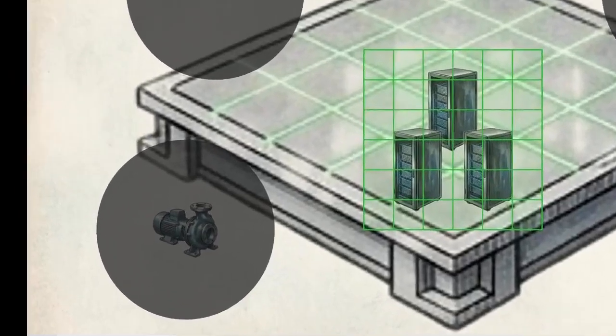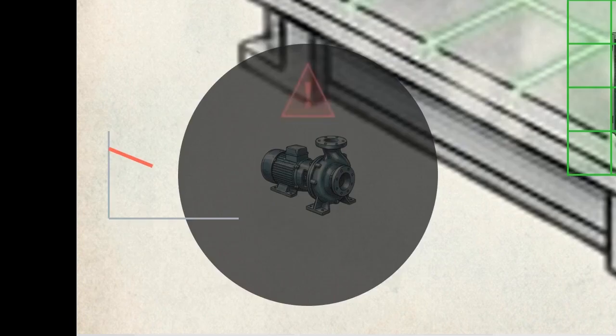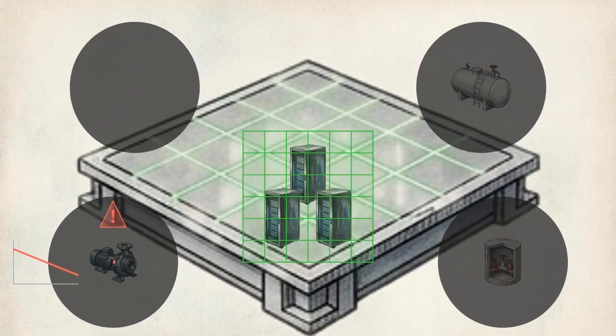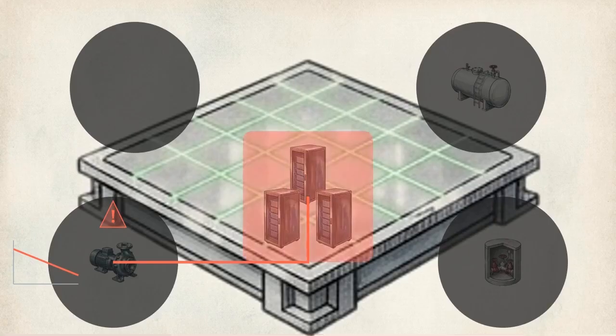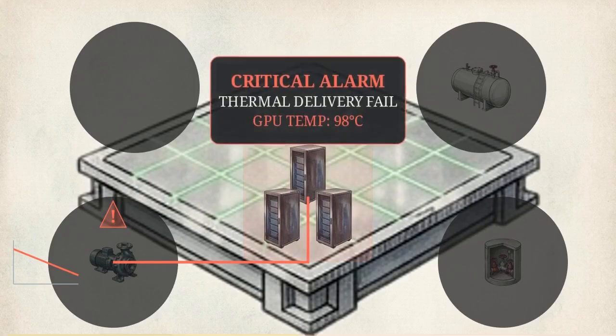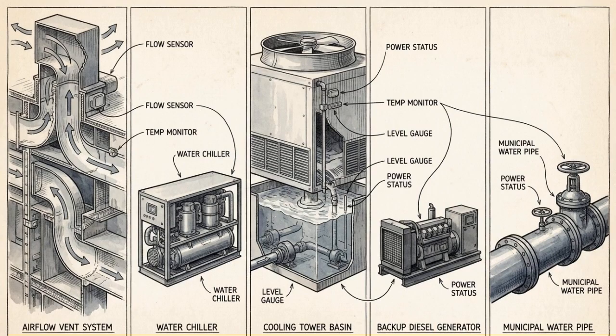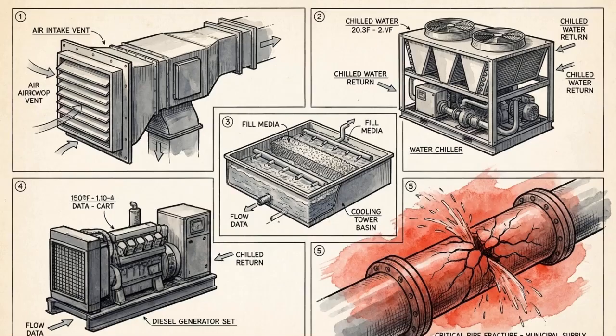Infrastructure problems begin as small deviations in these dark zones: a pressure reading dropping in a distant mechanical room, or differential pressure slowly rising across a strainer. Without telemetry, that deviation goes unnoticed until it cascades backward through the cooling loop, starves the server rack of its thermal delivery, and triggers a critical high-temperature alarm at the GPU. AI compute uptime requires continuous remote monitoring across 5 distinct domains of physical infrastructure. If any one of those layers degrades, the digital hardware is exposed.